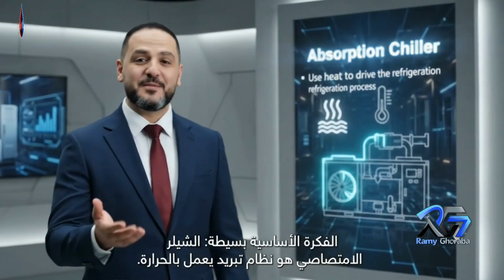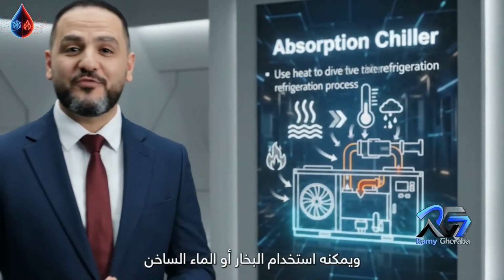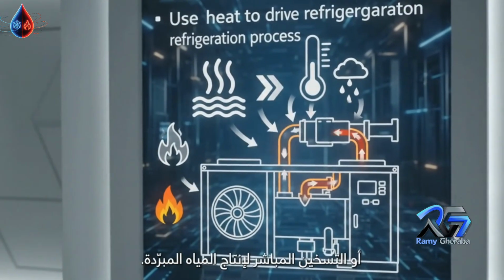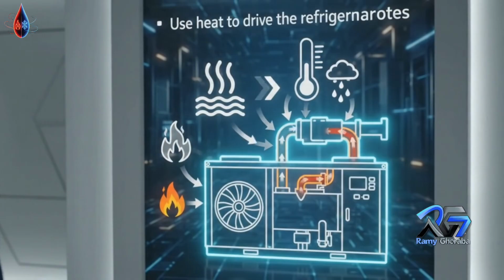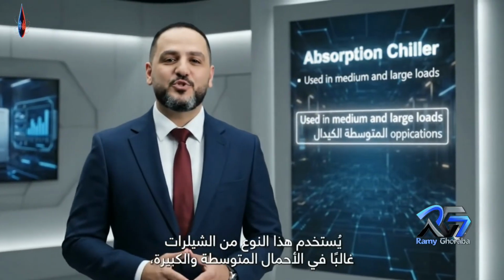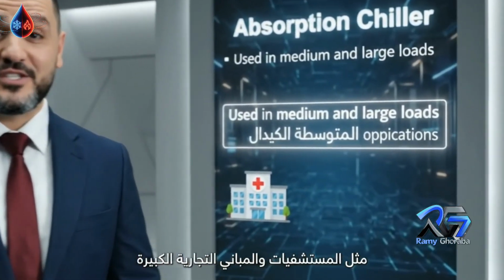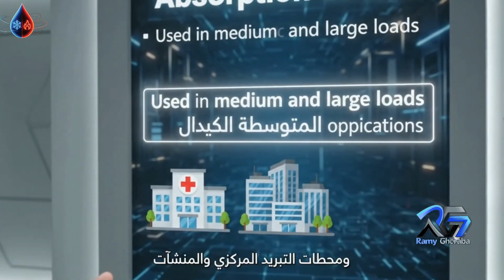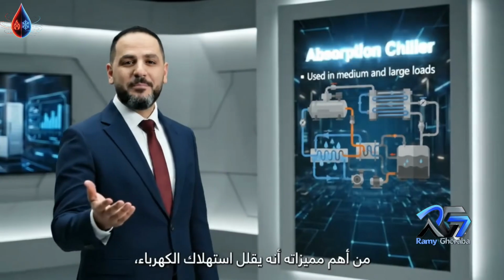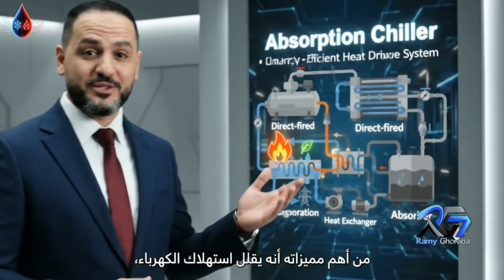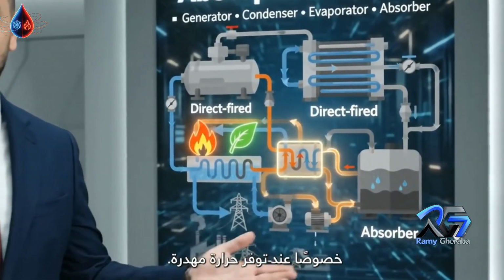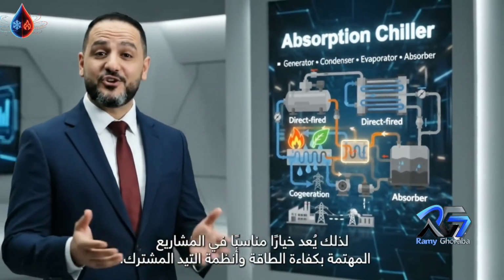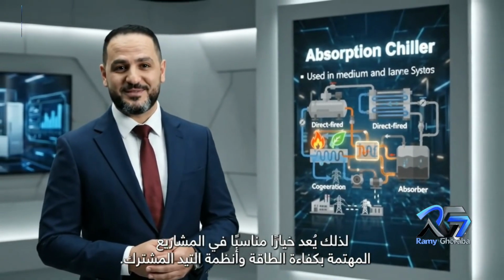The key idea is simple. An absorption chiller is a heat-driven cooling system. It can use steam, hot water, or direct-fired energy to produce chilled water. This type of chiller is mainly used in medium and large applications, such as hospitals, large commercial buildings, district cooling plants, and facilities with available waste heat. One big advantage is that it reduces electrical demand, especially when waste heat is available. That makes it attractive in energy-conscious projects and cogeneration systems.